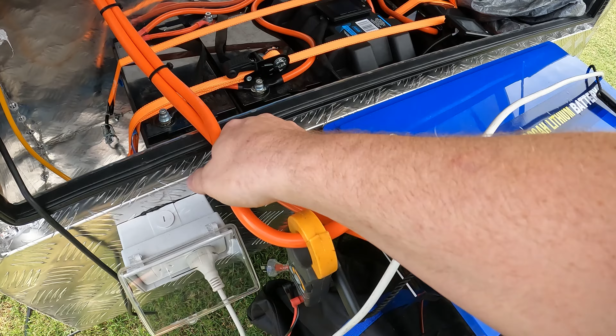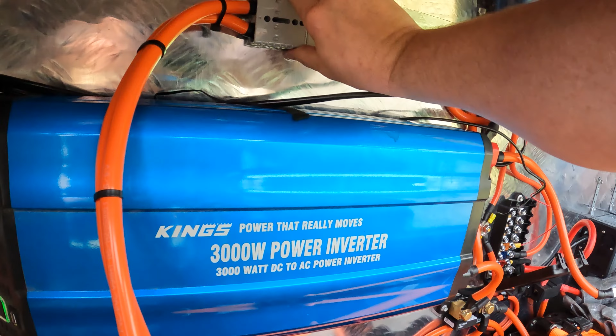You can definitely feel the heat here, and this is only 35mm cable. I probably should be running 50mm cable, and we're pushing a lot through the 175 amp Anderson plug. The cables are vibrating, it's using that much, but it's a good sign because it didn't cut out. It's just a little bit finicky, I suppose. So in my opinion, it'll probably pull the 300 amps continuous as long as you've got higher gauge cable.